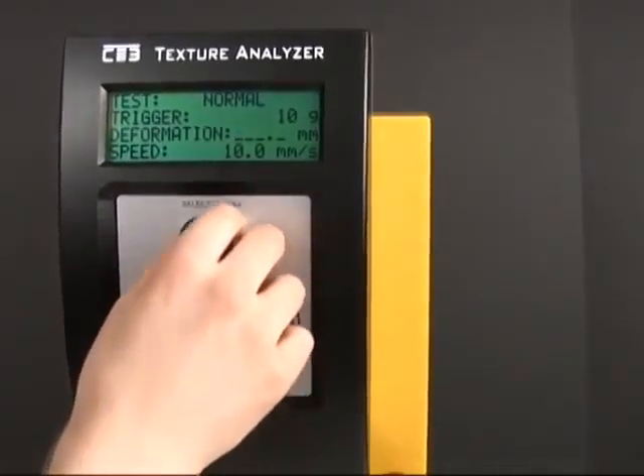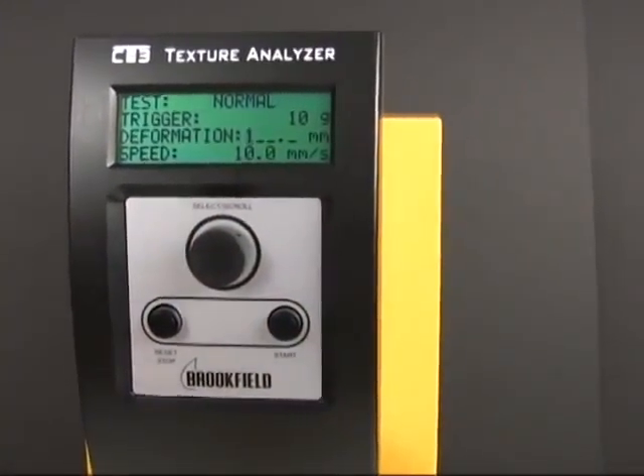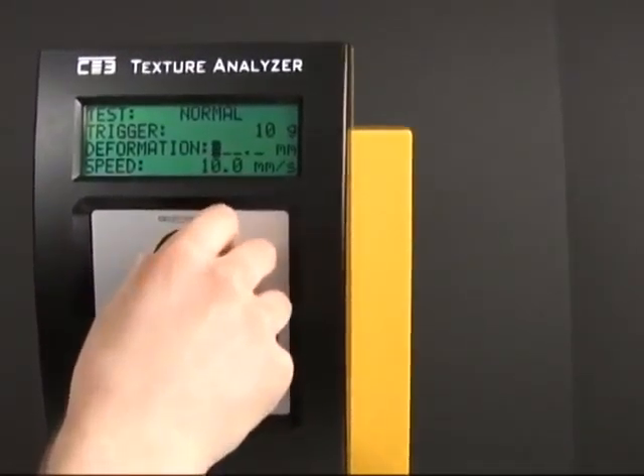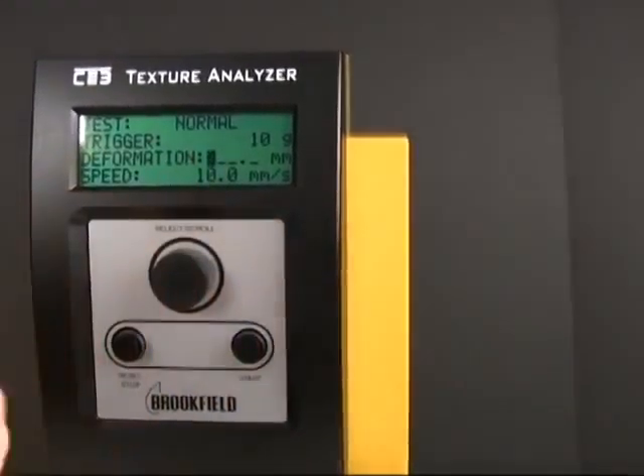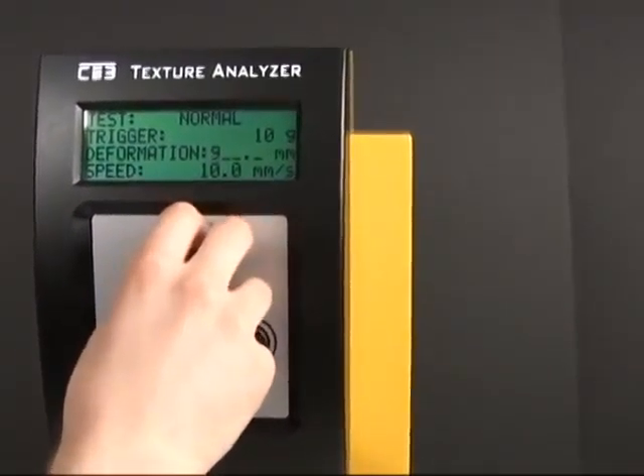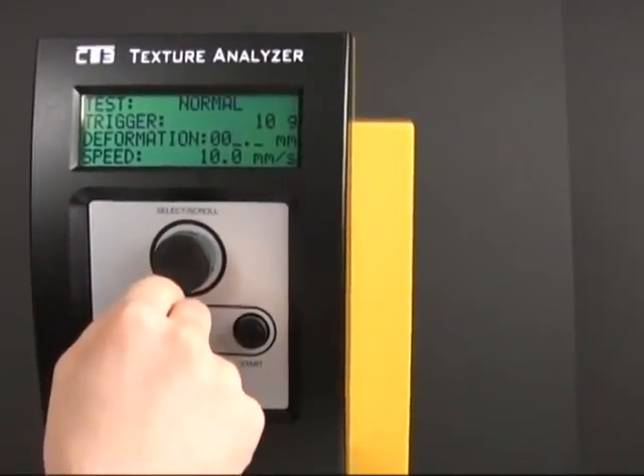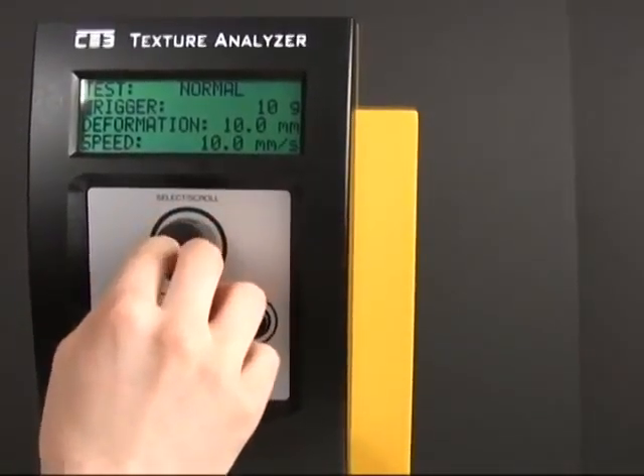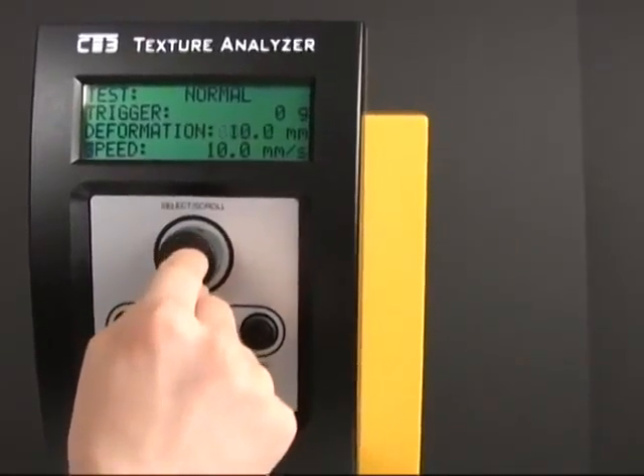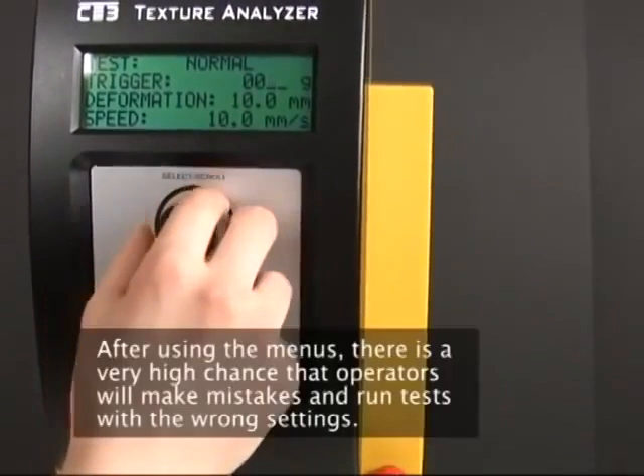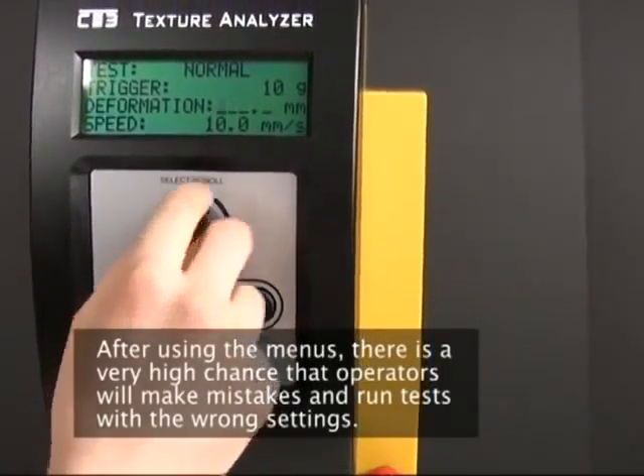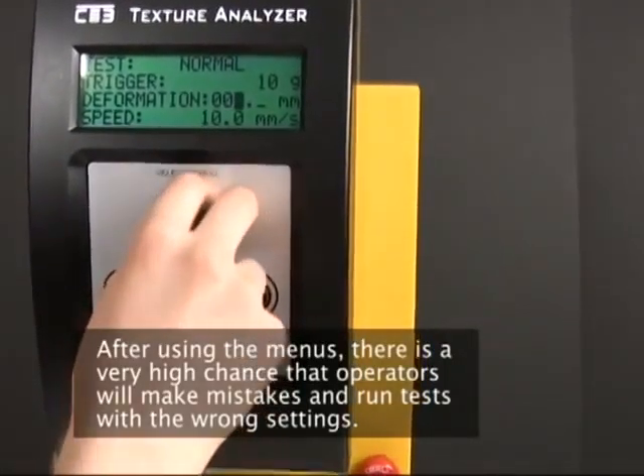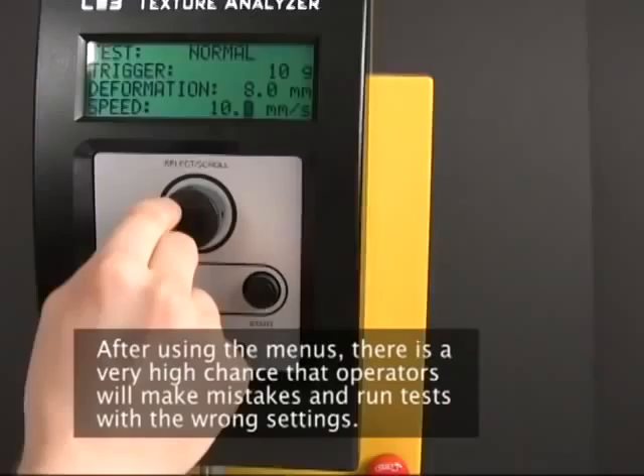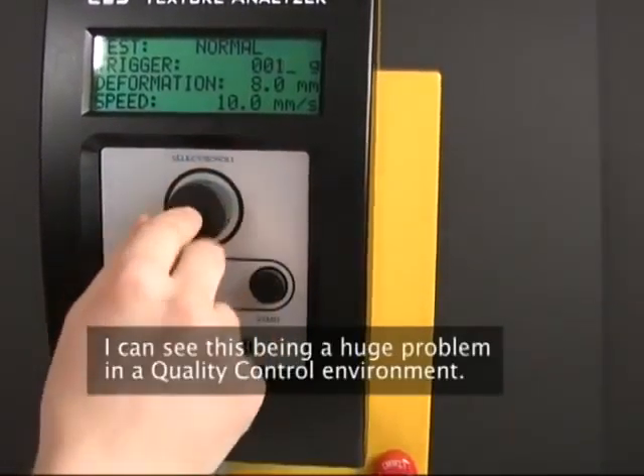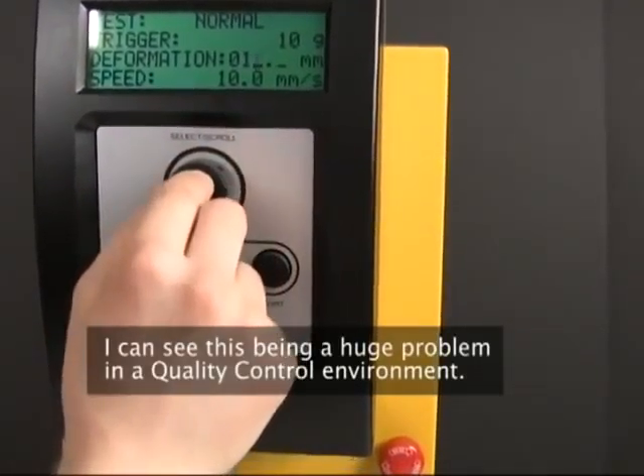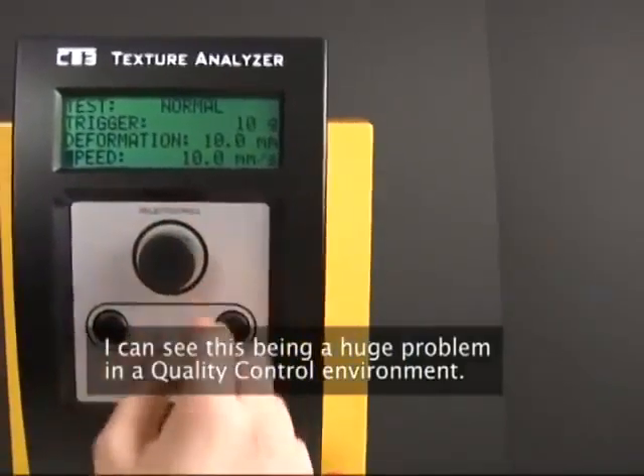Deformation, it's actually kind of funny because the machine allows you to set a deformation up to 999, but anything above 101, which happens to be the distance the machine can travel, is ignored, and it uses the last test settings instead. I'm going to do a 10 millimeter. Did that just default? Can I put it to 0? Yeah, that's it. Okay, 0, 0. Okay, 10 gram trigger. Speed, I'll just use 10 millimeters a second.